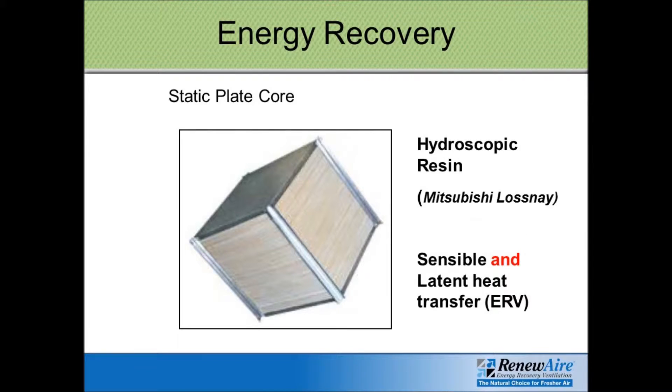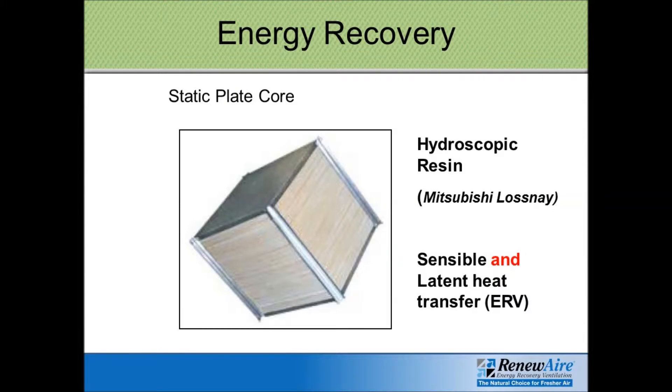Another type of static plate core — the one that Renew Air uses — is called a hygroscopic resin, a true enthalpic core. This has sensible and latent heat transfer: you can change the temperature of the airstreams, and you get moisture moving from one airstream to the other. So it's truly an ERV, an energy recovery ventilator, not just an HRV, a heat recovery ventilator. You may have heard the term Lossnay — this is a technology developed by Mitsubishi, and Mitsubishi does supply the cores for Renew Air. Everything else about the units is assembled in Wisconsin, in the Renew Air factory. The only thing they buy is the core from Mitsubishi, but it's a really high-performance, highly efficient core that transfers energy from one airstream to the other.